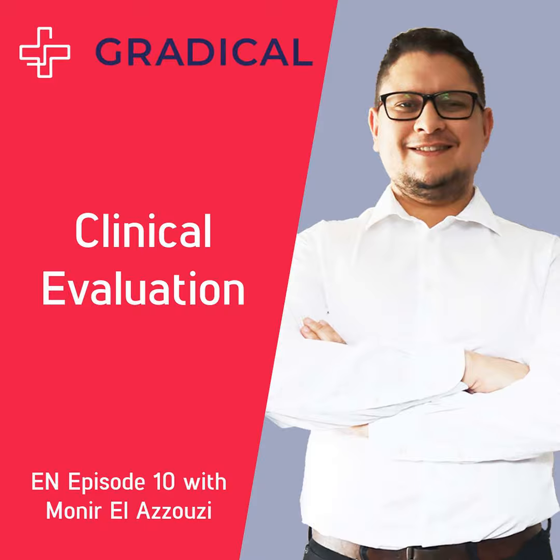Then we are planning within the clinical evaluation. We have two documents: the clinical evaluation plan and the clinical evaluation report. The clinical evaluation plan is a plan of how you will execute your clinical evaluation. You have to describe all the steps you will follow, for the literature, for example: which databases you will search, what keywords you will use, and how you will consider a product equivalent or not equivalent. So you will have to plan.